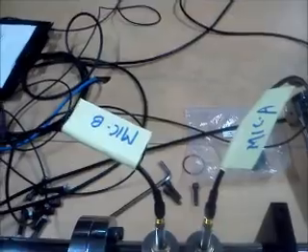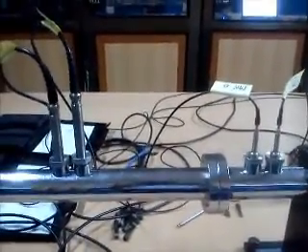Putting back all the microphones in standard position, mic A, B, C and D. So we now need to exchange mic 3 and 4, that is microphone C and microphone D. Just to show you, after changing microphones C and D, the series is A, B, D and C. So after changing microphones 3 and 4, we'll take the measurements.